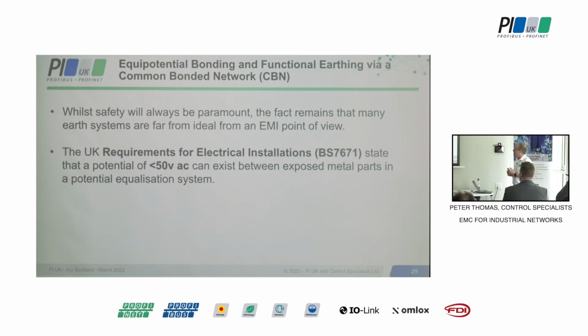And it's actually possible for two distinct grounds around a large installation to be up to 50 volts different. It's called a touch voltage, and that's long been the case. That's not a common reference. Common reference is very much less than a volt, millivolts.